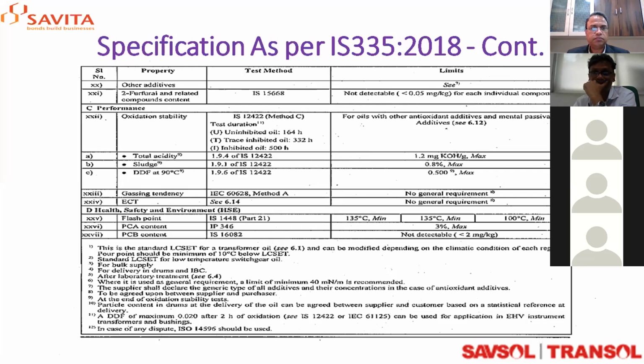Basically, the difference between type 1 and type 2 transformer oil is in viscosity. If you see IS 335, viscosity at 40 degrees Celsius for type 1 is around 12 CST, and for type 2 the limit is 15 CST. So viscosity difference is one of the things. Second is the pour point difference - it's understood that low viscosity oil will have a very good pour point, while higher viscosity oil will have an inferior pour point.